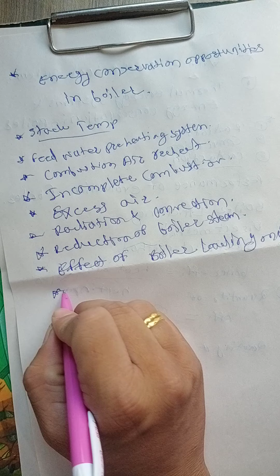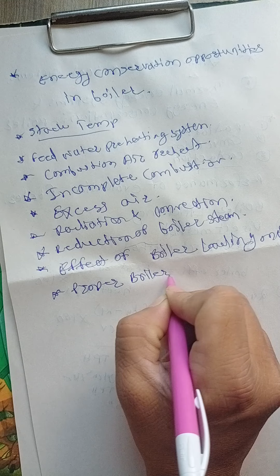Next, the last one is proper boiler scheduling. Since the optimum efficiency of a boiler occurs at 65 to 85% of full load, it is usually more efficient on the whole to operate a fewer number of boilers at higher loads than to operate a large number of boilers at low loads.